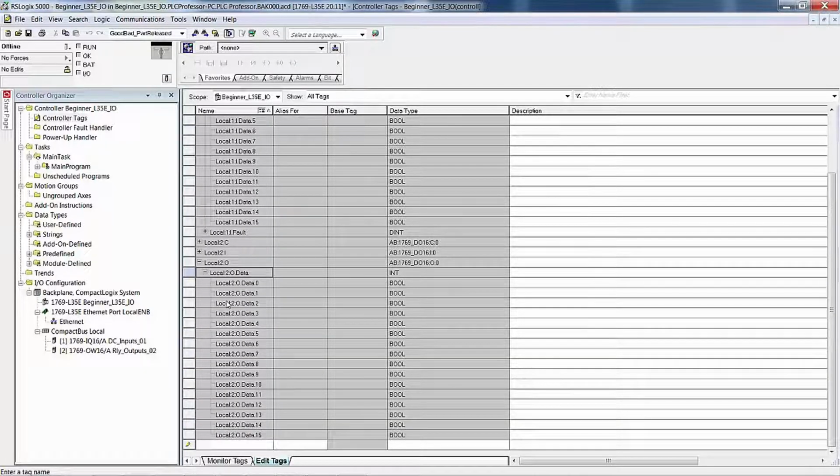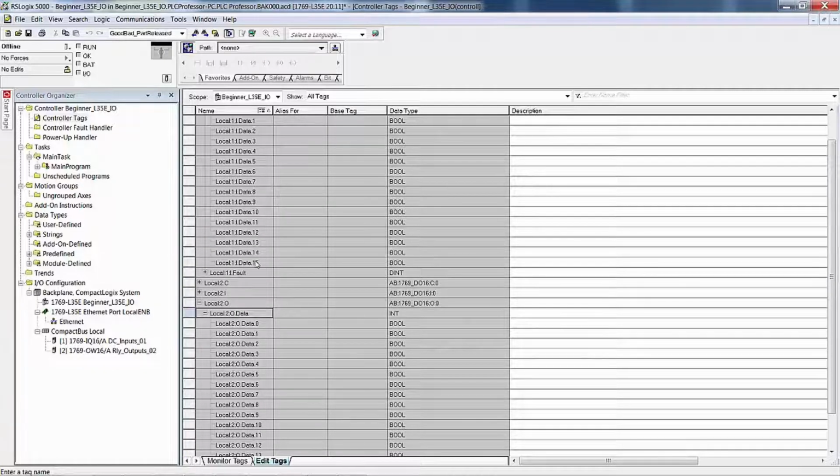Now this isn't like ControlLogix 1756 I/O, where your data words are dense and have 32 bits, even though you only have 16 actual inputs and 16 outputs. They're still made up of a DINT, and the other bits are hanging out in the breeze. They're just unused. In this case, all 16 of these are available for this kind of module.